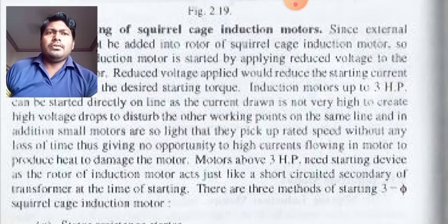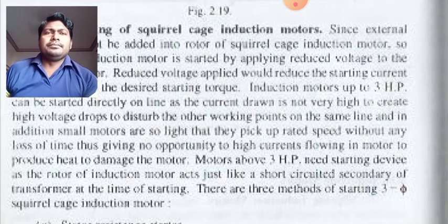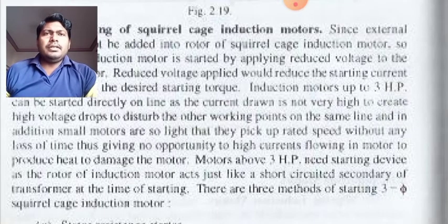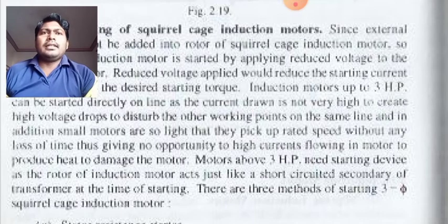Before going to the three methods, let me tell you students that if any motor is above 3 HP, as already mentioned, we have to go by one of the three methods which we will discuss. But what if it is lower than 3 HP? We can start it by a direct online starter, and by using it, the amount of current drawn will not affect the motor.